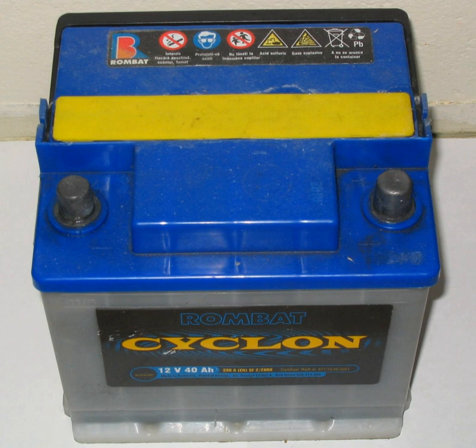In the absorbed glass mat (AGM) design, the separators between the plates are replaced by a glass fiber mat soaked in electrolyte. There is only enough electrolyte in the mat to keep it wet, and if the battery is punctured the electrolyte will not flow out of the mats. The purpose of replacing liquid electrolyte with a semi-saturated fiberglass mat is to substantially increase gas transport through the separator. Hydrogen or oxygen gas produced during overcharge or charging is able to freely pass through the glass mat and reduce or oxidize the opposing plate respectively. In a flooded cell the bubbles of gas float to the top of the battery and are lost to the atmosphere.